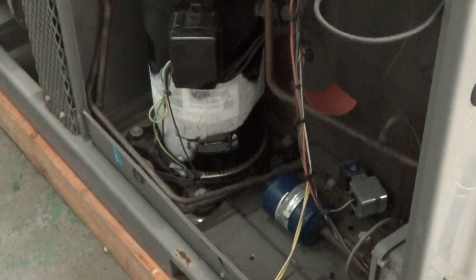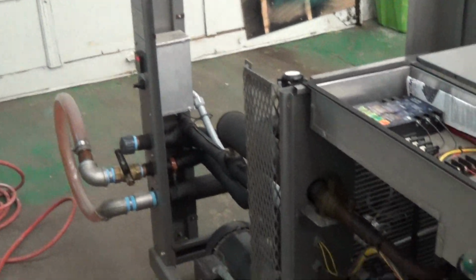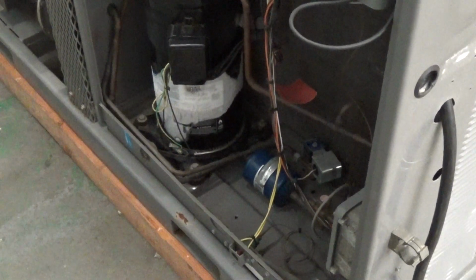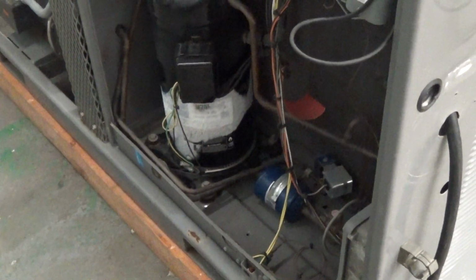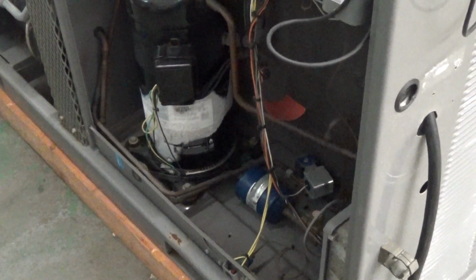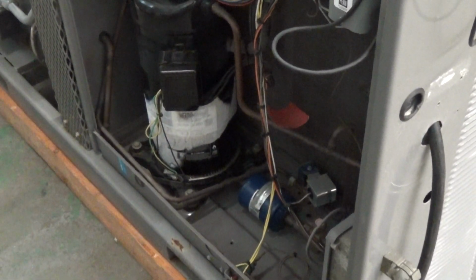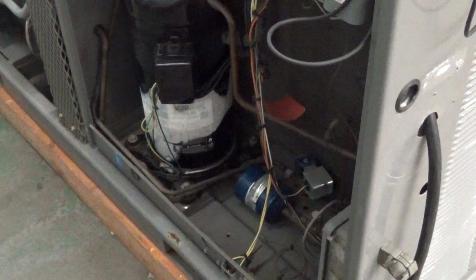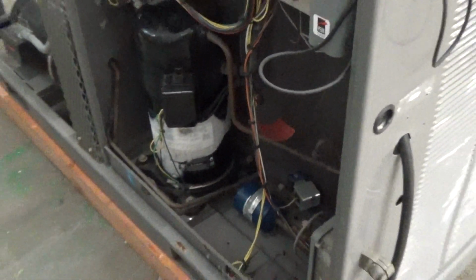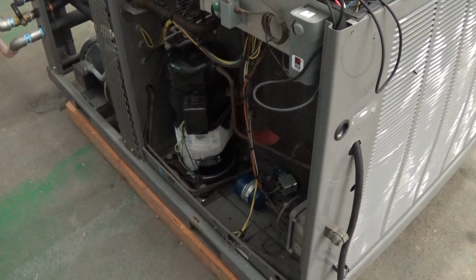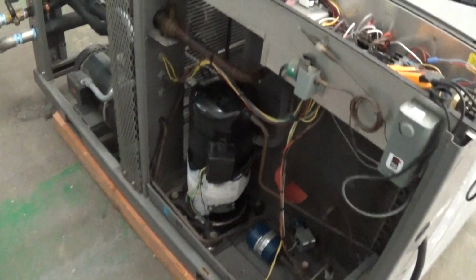With that said, you'll notice there's none building up at the very bottom. That's a heater band, a crankcase heater. That's always on. Even when you turn the power off on the chiller, as long as there's power coming into the unit, you always have power on that crankcase heater. So when you first get this chiller, it's important before you run anything that you allow that crankcase heater to be on and powered up for about 24 hours before you actually turn the chiller on. That way you don't get slugging and freezing and solidifying of the refrigerant just sitting idle there in the compressor.